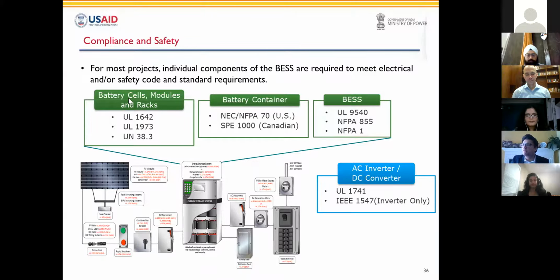So this slide shows the main codes and standards required to be followed by each subcomponent of the energy system. For battery cells, modules, and racks, you have UL standards 1642 and UL 1973 for safety. For battery container, you have NFPA 70. For the integrated battery system, you have UL 9540 and NFPA 855. And you'll hear a lot about these two, UL 9540 and NFPA 855. These are the latest safety standards, NFPA being National Fire Protection Agency. And then for AC and DC, for the power conditioning system and electrical requirements, you have UL 1741 and IEEE 1547, as well as any standards based on local jurisdictions like California's Rule 21 for inverters.